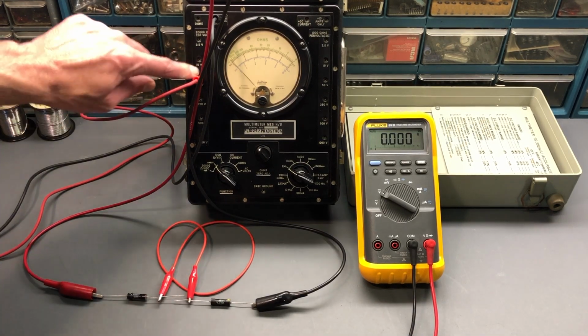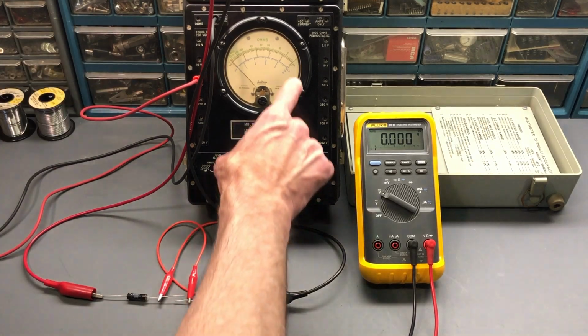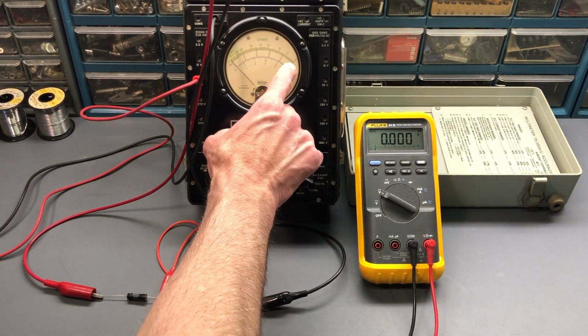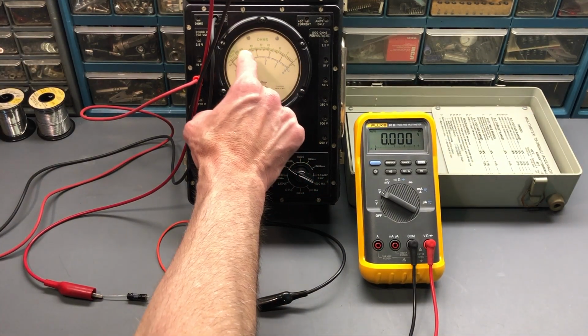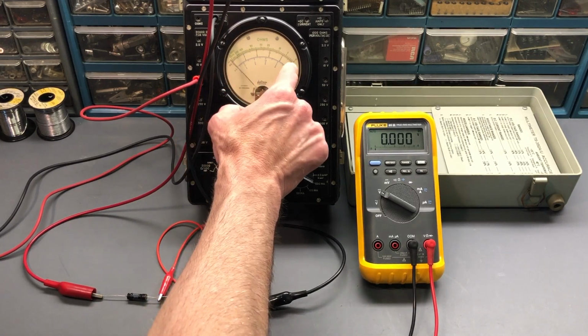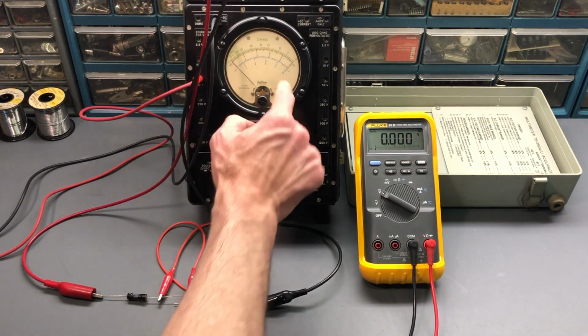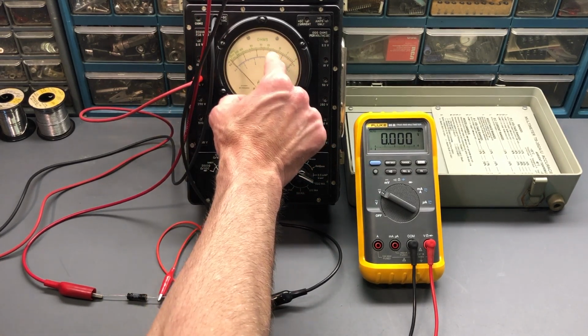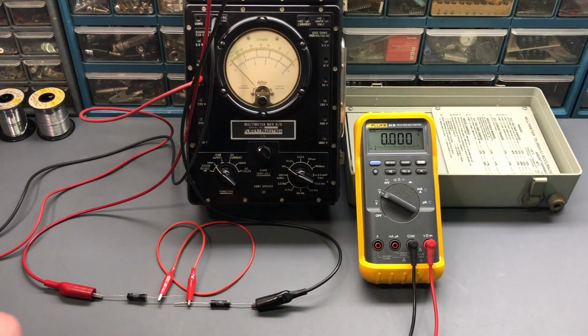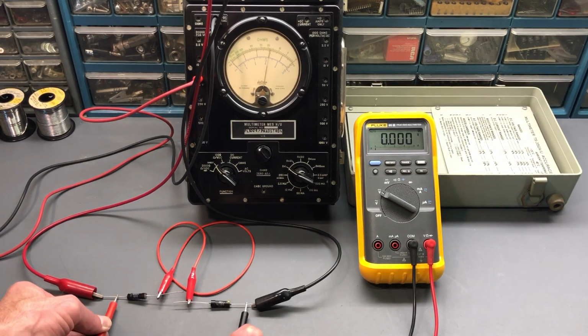So this is on the 50 range because it's on the 50 jack. So on the meter scale, you have 5, 4, 3, 2, and 1, and then 0. We're reading on the black numbers on the DC scale. Because it's on 50, the 5 becomes 50, 40, 30. So again, if 30 is right there, no problems. It's very, very close, right on that 30 mark.